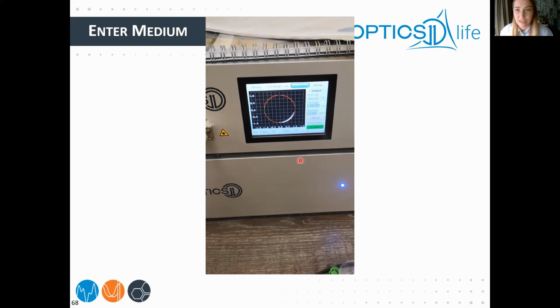So it gives an indication. Also, if the signal is gone while you are doing the measurements, which can happen, it just means it becomes like a point. It means your cantilever is in the wrong place. It's either stuck to the fiber or something like that, or you are indenting too deep into the sample. That's why it's like a point, because it's bending so much that there's no signal anymore.